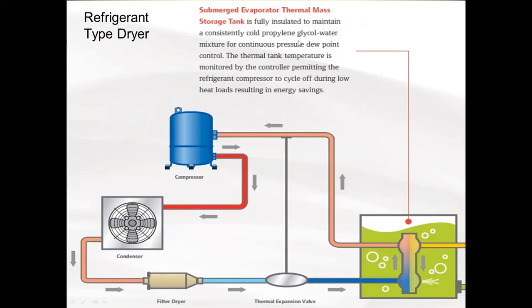This is what's called a thermal mass type dryer. The thermal mass is down here inside this tank, and it's usually glycol, because 35, 37, 38 is pretty close to freezing, and we want to make sure that we don't freeze this thing up. With the glycol and water solution, the more glycol, the lower you can push the freezing point, to 0 or below. That's Fahrenheit. So we don't have to worry about freezing this tank if it's glycol.